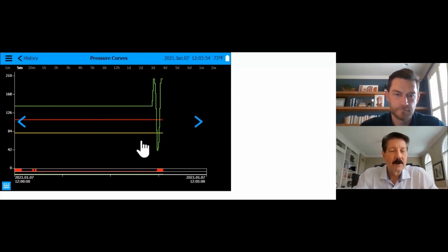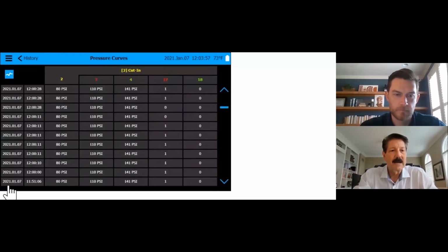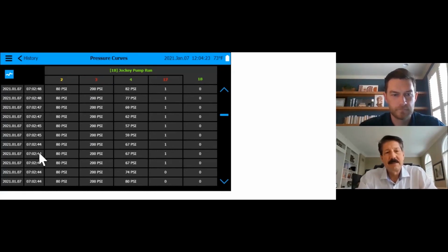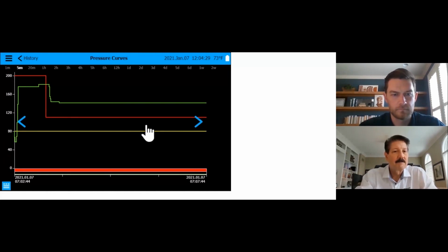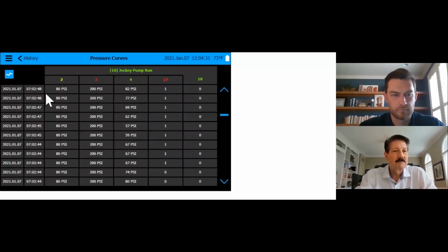Now, for people that aren't so tech savvy, you can go to the bottom left side and convert it to a spreadsheet. And so here's your date stamp and time. Here's your cut in, 80 PSI. Your cut out was 110. Your system pressure was at 141. Anytime 17 has a 1 under it, it shows that the motor's running. Anytime 18 has a 1 under it, it shows the jockey pump is actually operating. So again, this makes life much simpler and easier, you can convert it from actual curves to a spreadsheet that's downloadable.